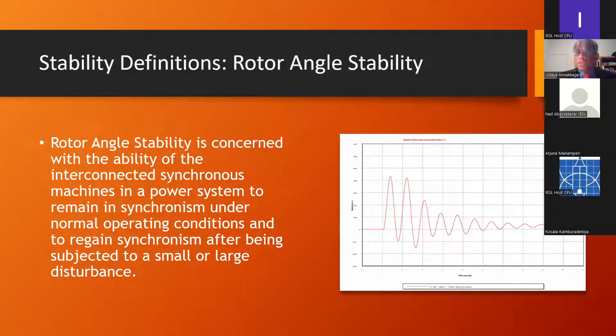So there are two things here. In a synchronous generator, there's an electromagnetic torque, and the torque can be resolved into two components in quadrature. One is called synchronizing torque, and the other component is called damping torque. So the initial swings of the machine, the speed increasing, reaching a peak and coming back, are because of the synchronizing torque, and the subsequent damping is due to damping torque. So for stability of a synchronous machine connected to a grid, one needs both synchronizing torque and damping torque. And damping torque is one of the big topics in stabilizing a power system. This can be achieved by adding auxiliary controllers to the excitation system of the machine.